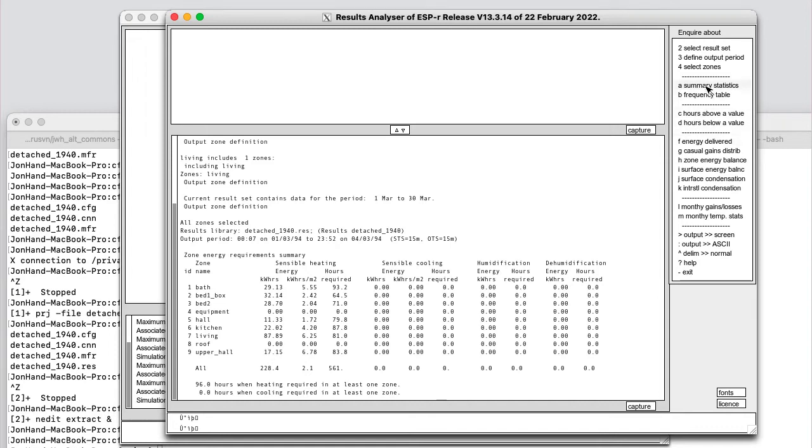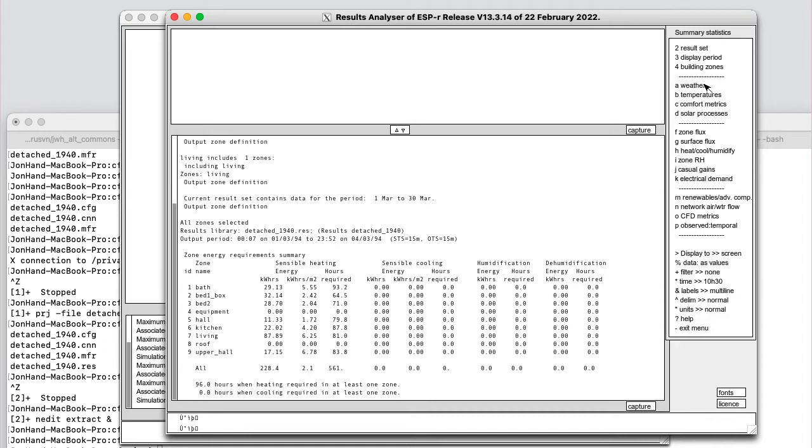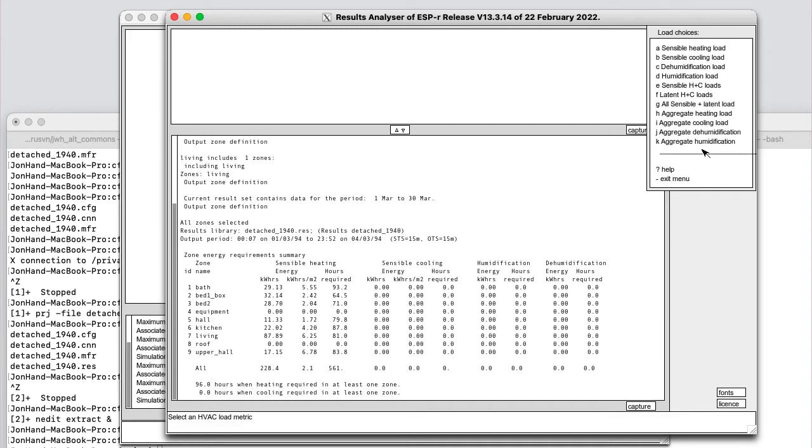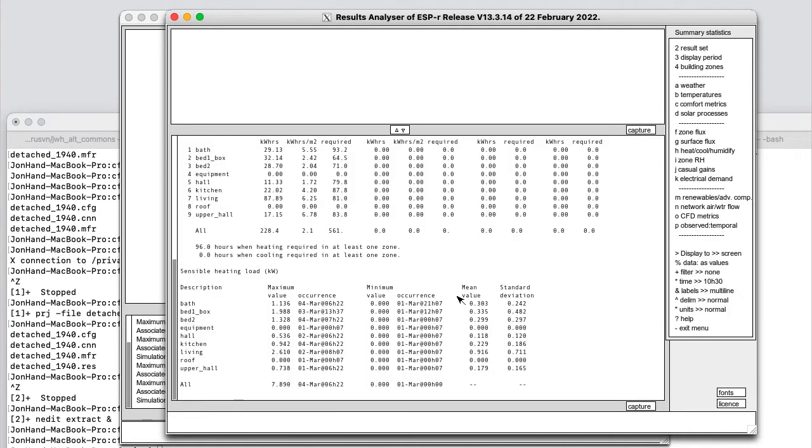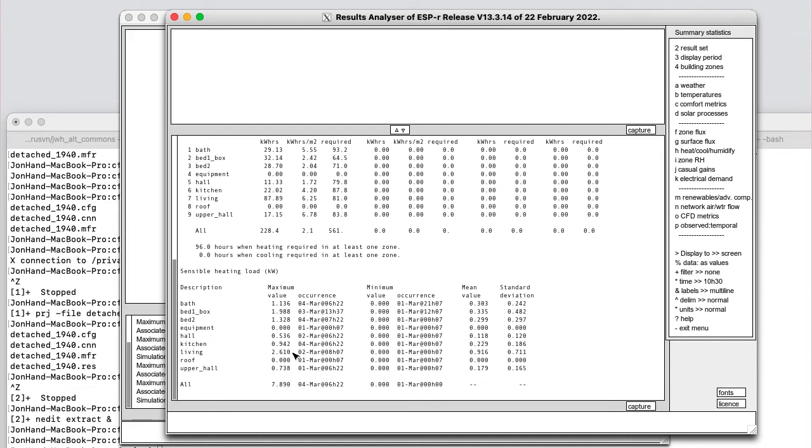Let's look in summary statistics. For example, we've got an item here, heat, cooling, humidify, and we can get the sensible load in each of the zones, and this is another classic ESP report. So units in kilowatts, what's the maximum, when does it occur, what's the minimum, when does it occur, mean, and standard deviations. And then we have a diversified total at the bottom, and the time when that occurred.